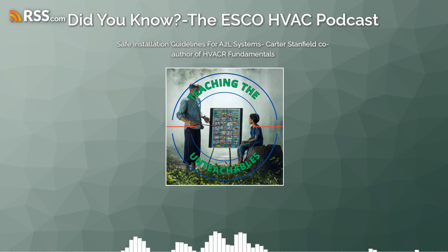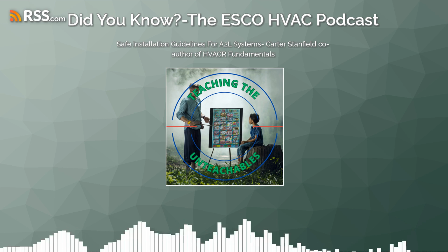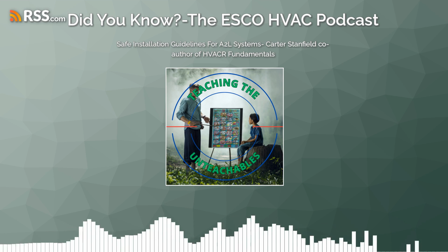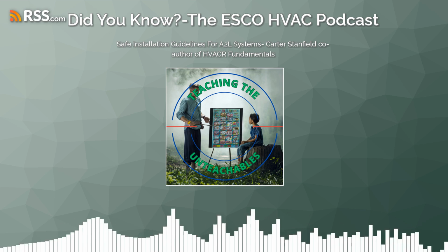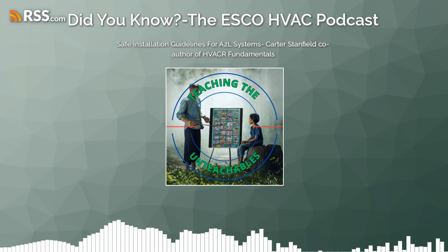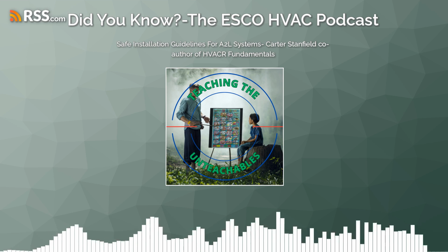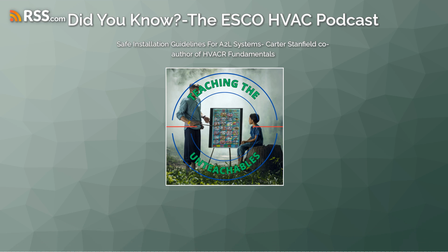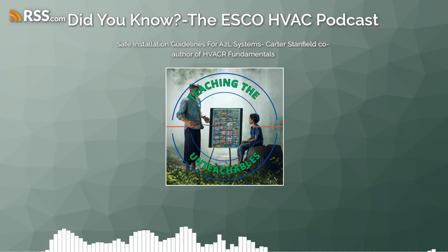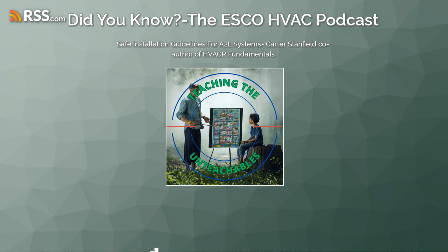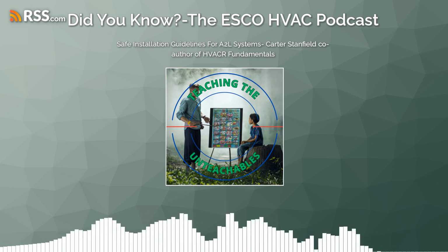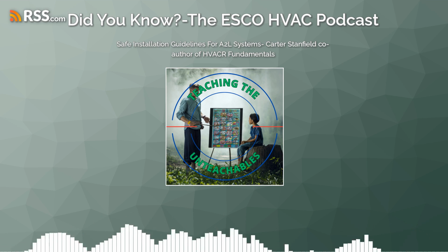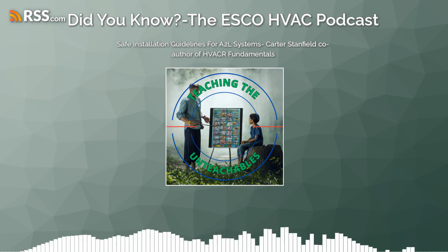So that's where we get into the mitigation, and the amount of mitigation and the type of mitigation varies based on the quantity of refrigerant and the application. Yeah, a lot of people don't realize that, like you'd mentioned before, a lot of our window units and PTAC units have already made the transition to A2L refrigerants. Pretty much any window air conditioner you buy right now has R32 in it. Same with the PTACs. Yeah, you'd have a hard time actually finding a window unit that doesn't have R32 in it. Exactly. And because of that charge limit of around 4 pounds, most of those window units have a pound or under of refrigerant, so they have no additional requirements for mitigation.